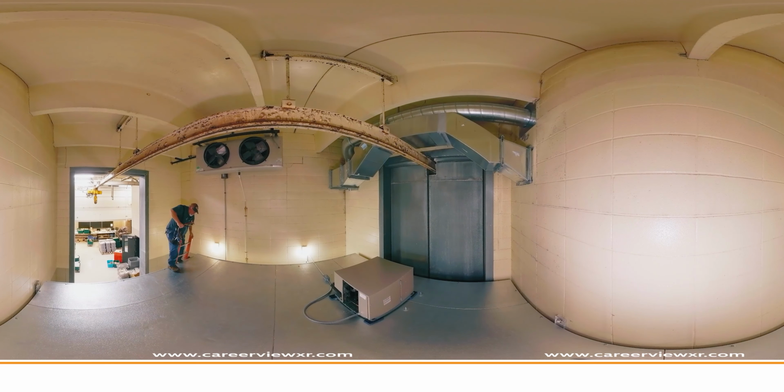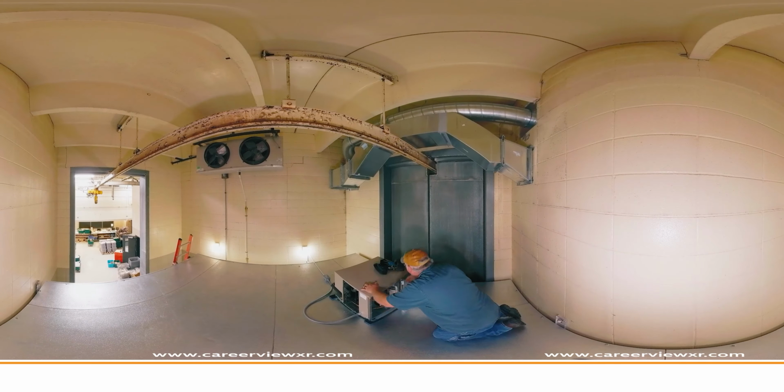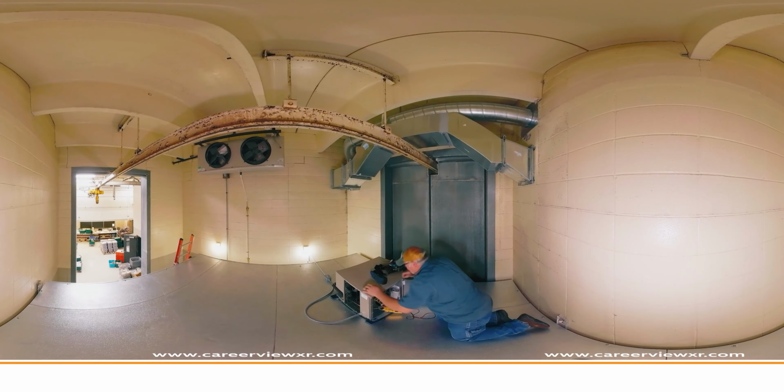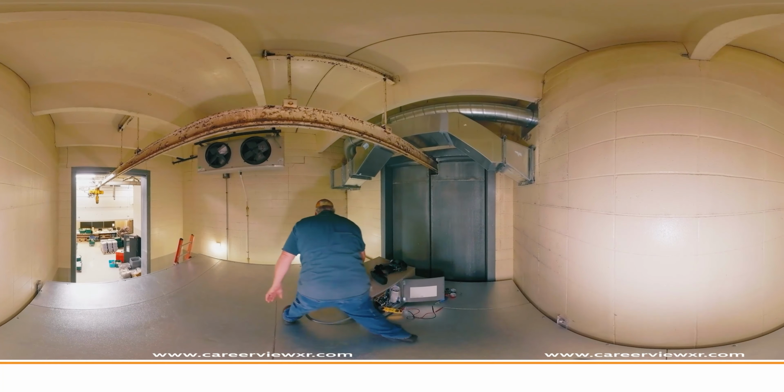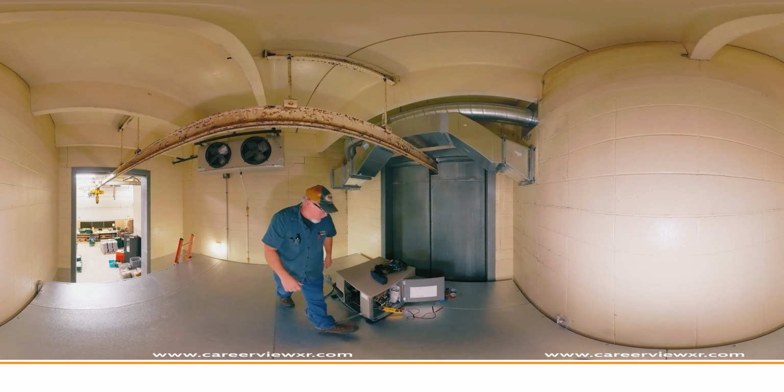The condensing unit is on top of the walk-in cooler. Craig climbs the ladder and removes the electrical cover to check the power and control components. He checks the electrical voltage and the refrigerant flow level. Craig decides he needs to reset the controller on the evaporator.